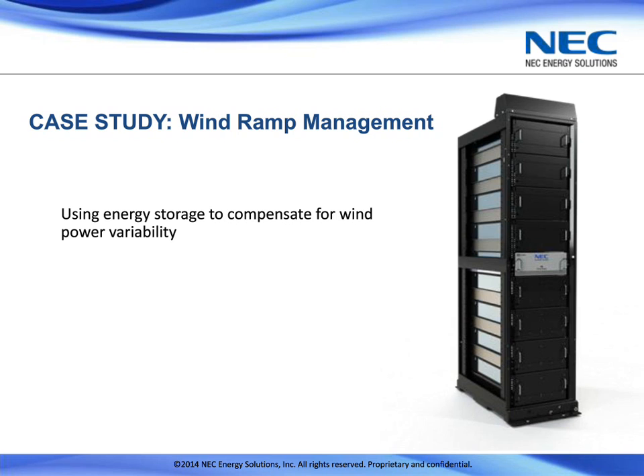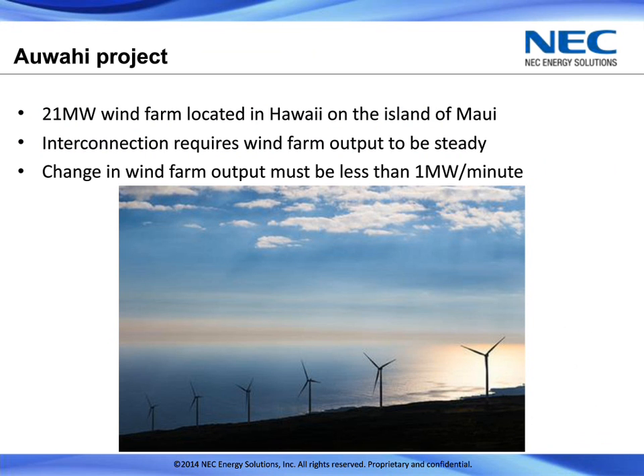So in this case, we are looking at a project on the island of Maui in Hawaii. And for context, the island of Maui is getting to the point where if all of its renewable generation ran at its full output, and they were operating at their minimum load point on their grid, they would be getting very close to saturated, to full penetration. It's a fairly unique situation.